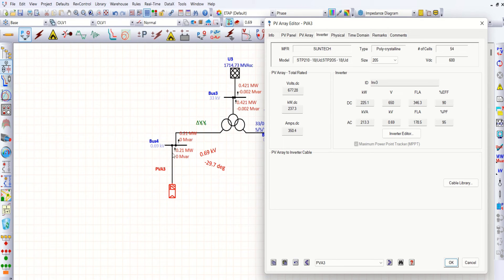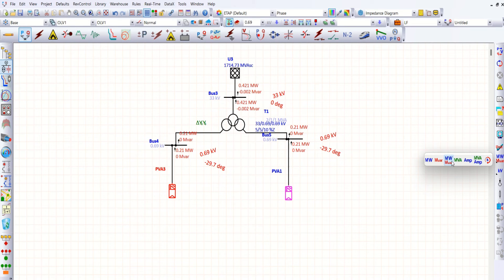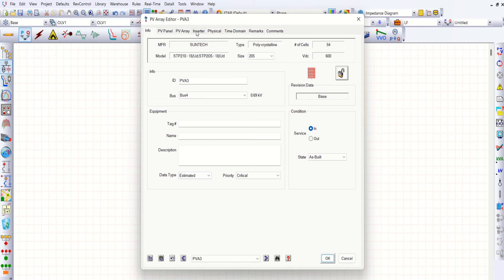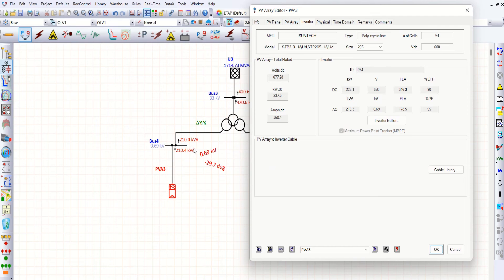You can exactly match this value. Let me go for kVA — the kVA value alone is available. Approximately 210.4 kVA, and 420.6 kVA for both combined, which is what you could see here. We rated at 213 kVA but are getting 210.4 kVA because of power factor and efficiency all put together.